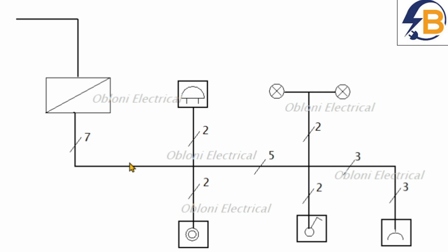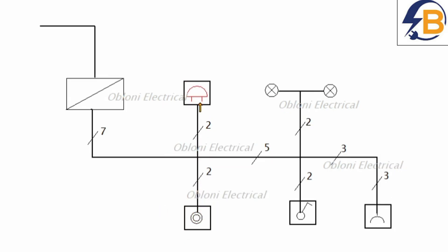Moving to the next branch: it's very simple — we have a feed from the board to the bell switch and then another wire that goes to operate the bell. Here also we have two wires through this branch: one is the feed from the board and then a switch wire that goes to switch the lamps. There are five wires here already — the three wires that pass to the socket, plus one feed wire and one neutral wire.